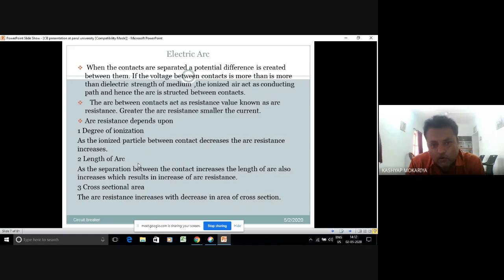Take what they are doing in a 440 volt LT breaker that is rated for operating a motor of 90 kilowatt to 160 kilowatt. I have to lengthen the arc through my arc chute chamber, which I'll be showing in the presentation later, and through that process I am increasing the arc resistance of the breaker and thereby extinguishing the arc. But imagine, can the lengthening of the arc be useful for high voltage breakers? The answer is no, because if you lengthen the arc, you put your fixed and moving contacts at a particular distance, or you put splitters there, and your size will be uneconomical. Those high voltage breakers will be very bulky if the voltage rating is increased to take care of these things.